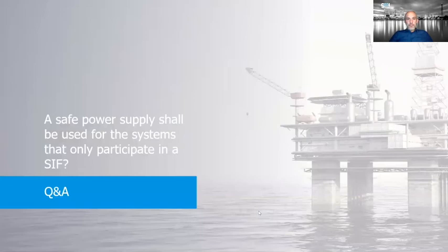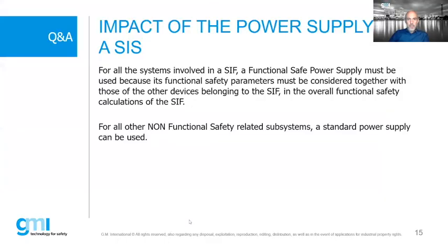Okay, and again, we have another question. Typically, should a safe power supply be used only for the system that participates in a SIF? Yes, of course, we have repeated it a lot of times. For all the systems involved in the SIF, a functional safe power supply must be used because of the functional safety parameters. The parameters of the power supply have to be considered together with the other devices belonging to the SIF. So that is fundamental.